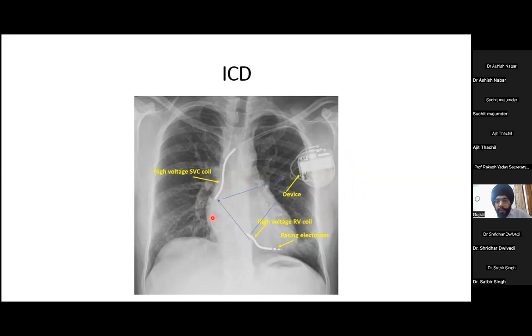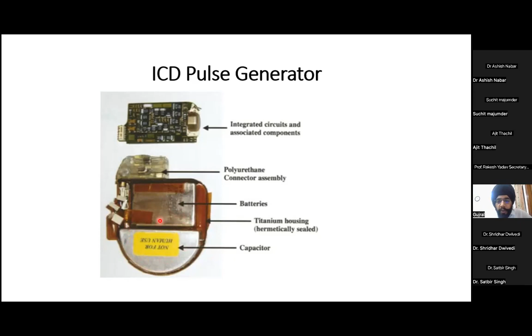Coming to the pulse generator, the difference compared to a pacemaker is that in addition to the battery, there is a capacitor. What is the importance of a capacitor? Just like a pacemaker, it is supposed to deliver charge, but it has to deliver a huge amount of charge in a very small interval of time, within 5 to 7 seconds. So it needs to store charge and discharge it as quickly as possible. That is where the role of a capacitor comes in.